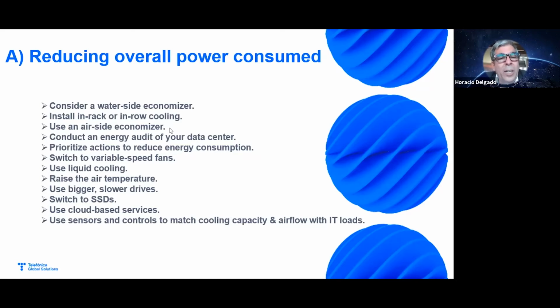Some simple things that can be done: switch on server side to variable speed fans, instead of running fans at 100%, to use less electricity. Use liquid cooling also. The next one, which is quite effective and I believe most data centers do, is to raise the air temperature a little bit. Servers don't need to run at 65 degrees Fahrenheit; they can run at a higher temperature and nothing will happen to them. So that's something that can be controlled and is quite effective.